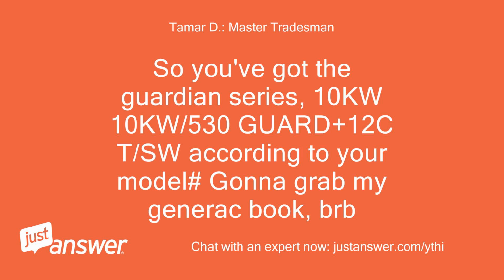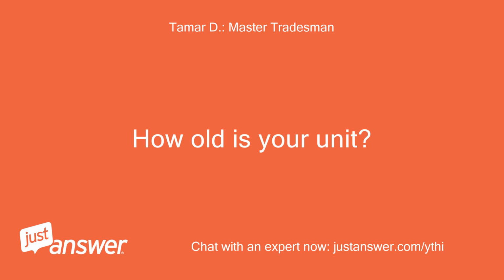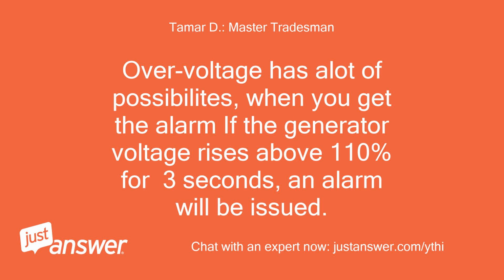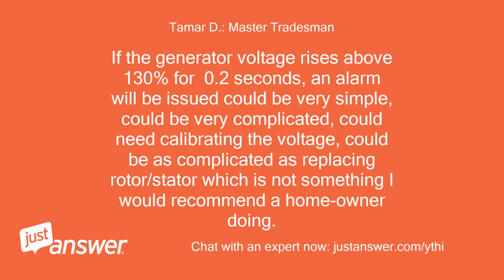So you've got the Guardian series, 10 kW, according to your model number. Gonna grab my Generac book, BRB. How old is your unit? Over voltage has a lot of possibilities. If the generator voltage rises above 110% for 3 seconds, an alarm will be issued. If it rises above 130% for 0.2 seconds, an alarm will be issued. Could be very simple, could be very complicated, could need calibrating the voltage, could be as complicated as replacing the rotor/stator, which is not something I would recommend a homeowner doing.